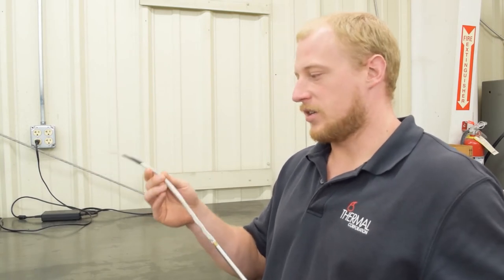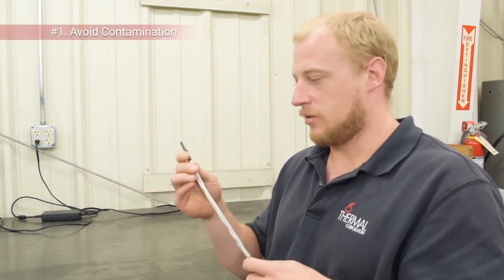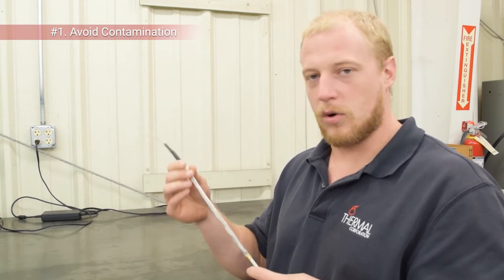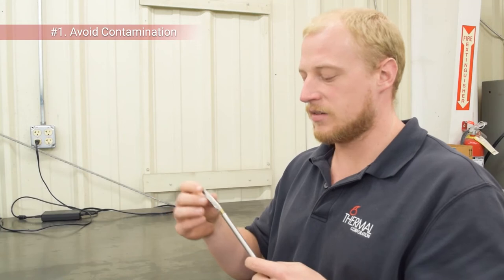The first and foremost thing is you want to avoid contamination of your heater. You don't want to get any water, moisture, oil, plastic, or anything on the leads or down in the end of the heater. That's really bad.